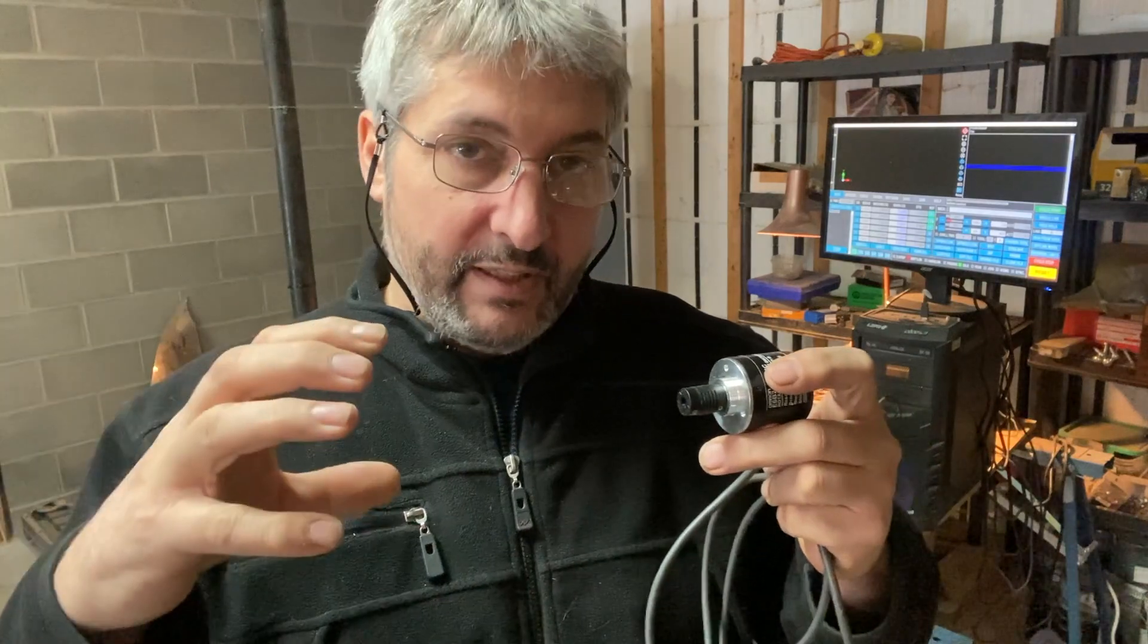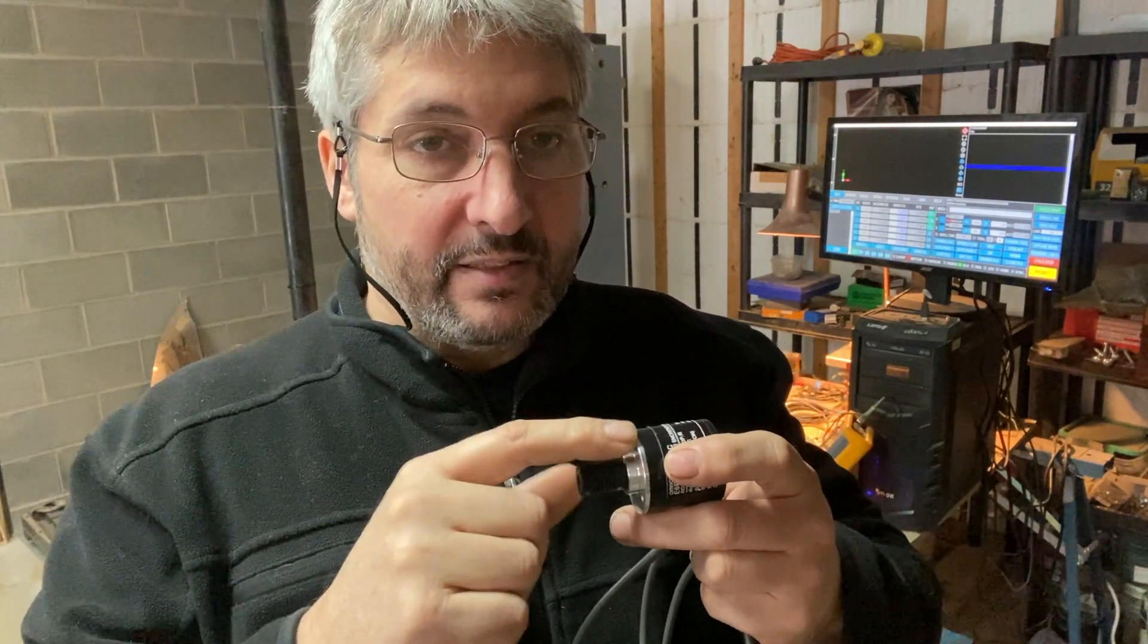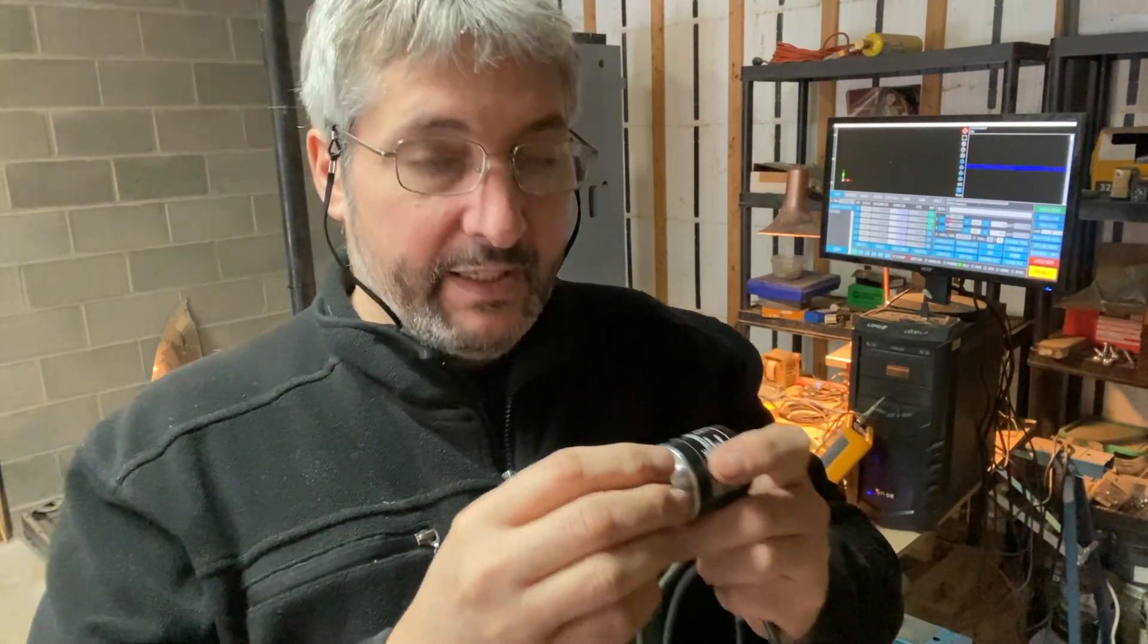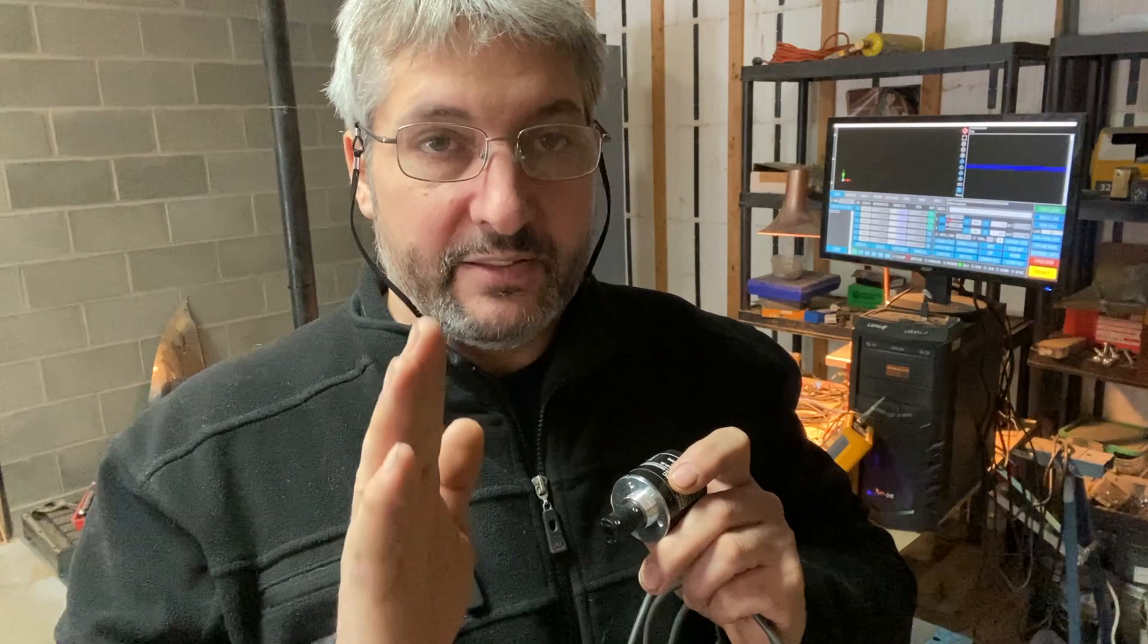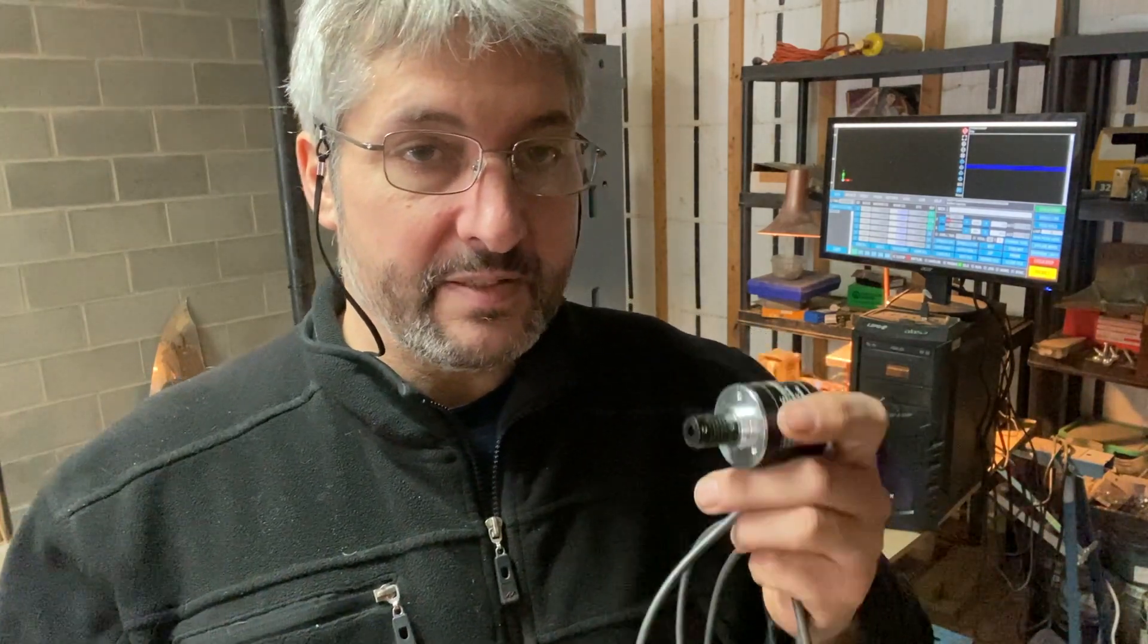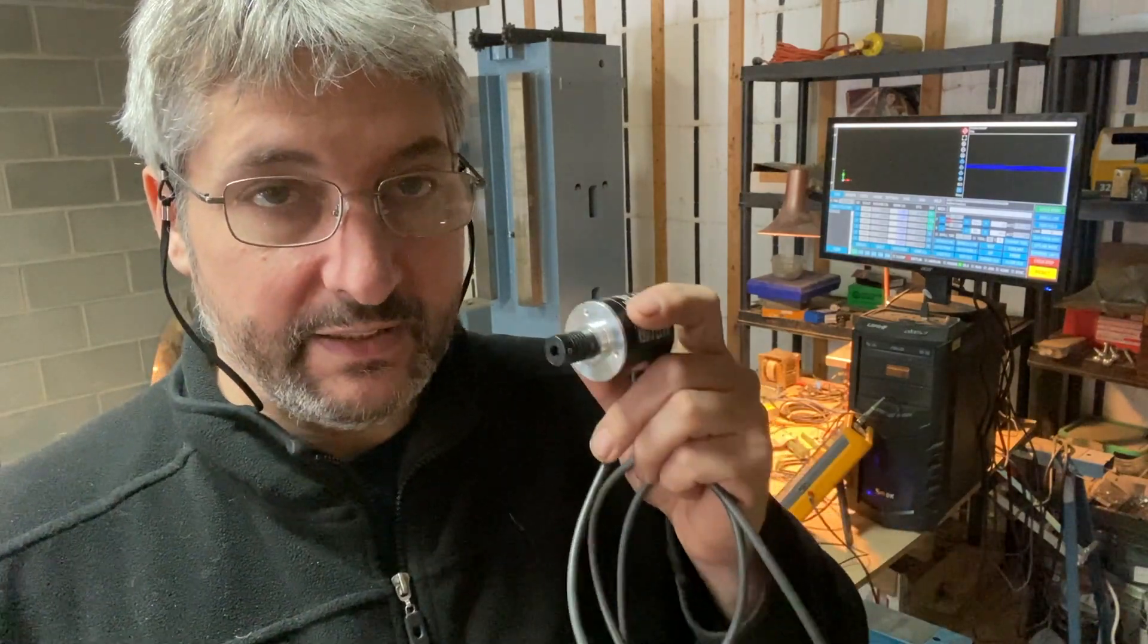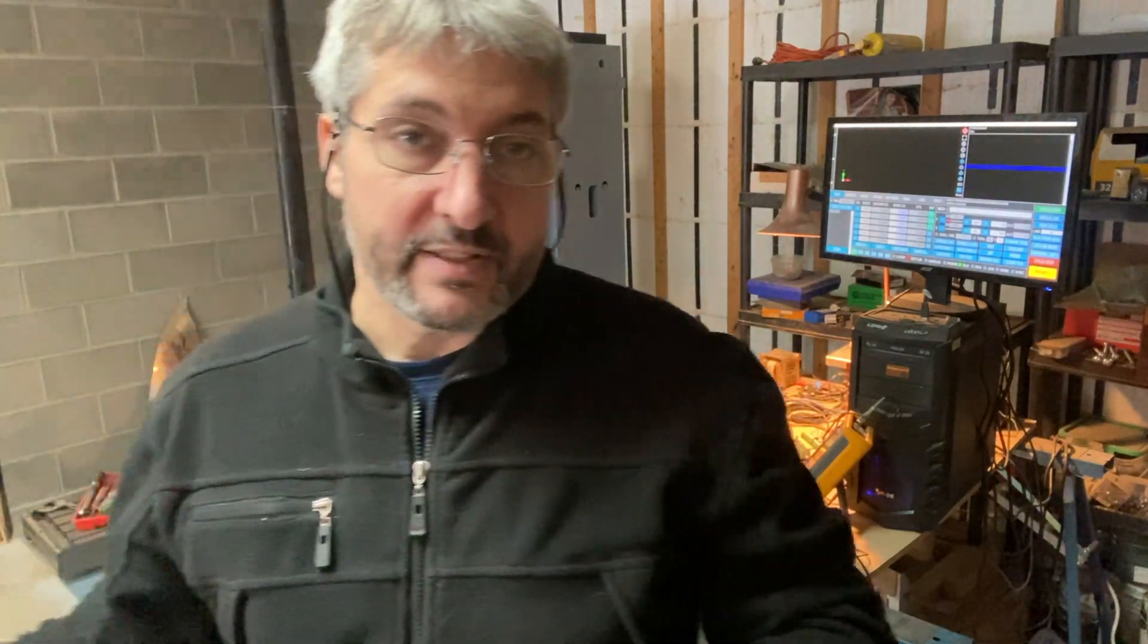The motor is making the screw turn so the axis is still moving until it hits the index of the encoder. This is the homing. The index of the encoder will always be very precisely at the same place. It doesn't vary at all. This is the ticket for precision homing, using the index of the encoder.